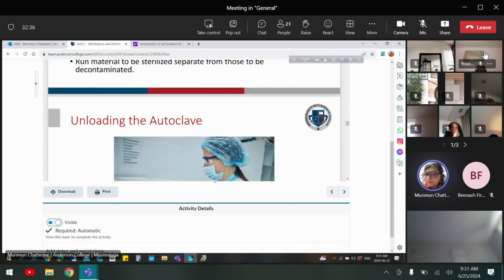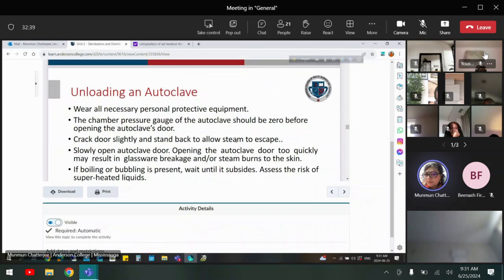Unloading the autoclave. First you have to release the pressure. When the pressure and steam have come down totally to zero, then wear all the necessary personal protective equipment. The chamber pressure gauge of the autoclave should be zero. When the autoclave is done, the pressure is going to be reduced, you need to turn off the autoclave, and it is going to go down to zero. Until it reaches zero there is huge pressure inside, and if you try to open it, it is going to prevent you from opening. But in case you open it, there will be huge hot air and you are going to get a steam burn.